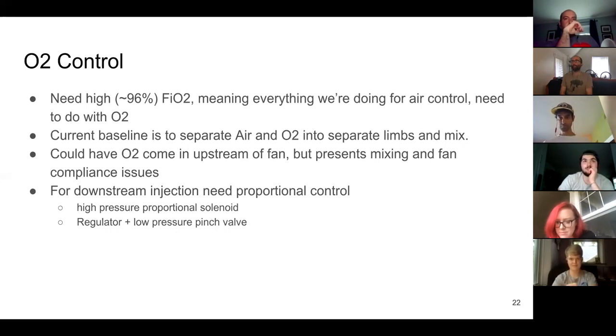So everything we've done for air control, we pretty much need to do in parallel for oxygen control, because at 100% FiO2 there's no air, so the fan isn't really doing anything. Current baseline is separate air and O2 with a separate limbs to mix. We could have the O2 come in upstream of the fan, but there are concerns around that, mainly the mixing and the fan compliance.